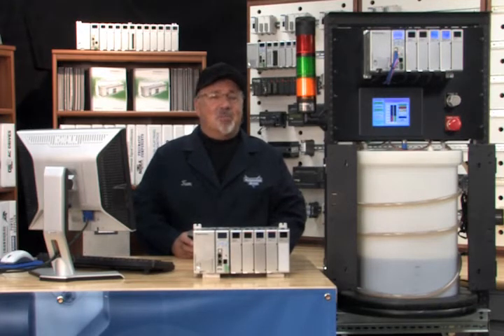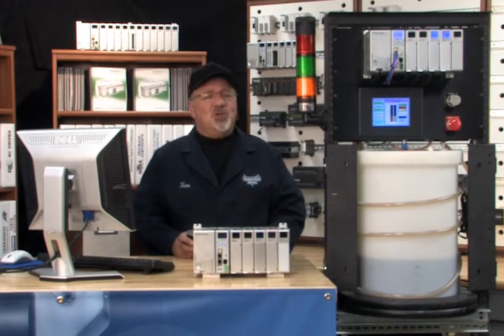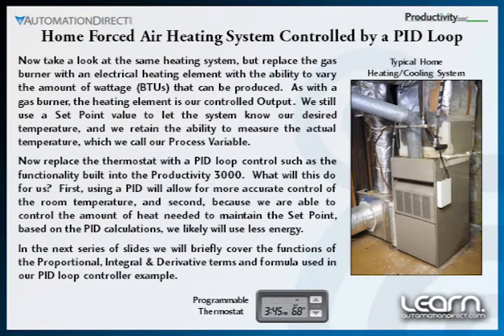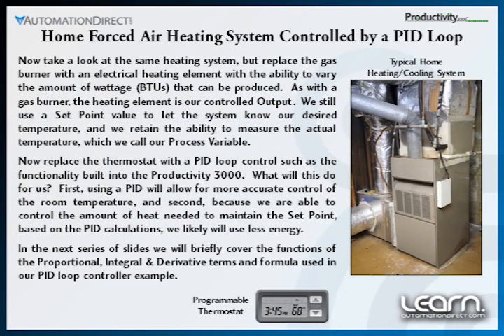Using the same heating system, but instead of an on-off gas burner, we'll use an electrical heater. The electrical heater is controlled with a variable power device that can adjust the heating's wattage output, or BTUs, from zero to full output and anywhere in between. Next, replace the thermostat with a PID loop controller. We still have our set point to fix our desired temperature and the ability to measure the actual room temperature — our process variable — but now we can control the amount of heat we need based on the PID loop's calculations. This ability will produce a more constant result and, in the process, most likely use less energy.